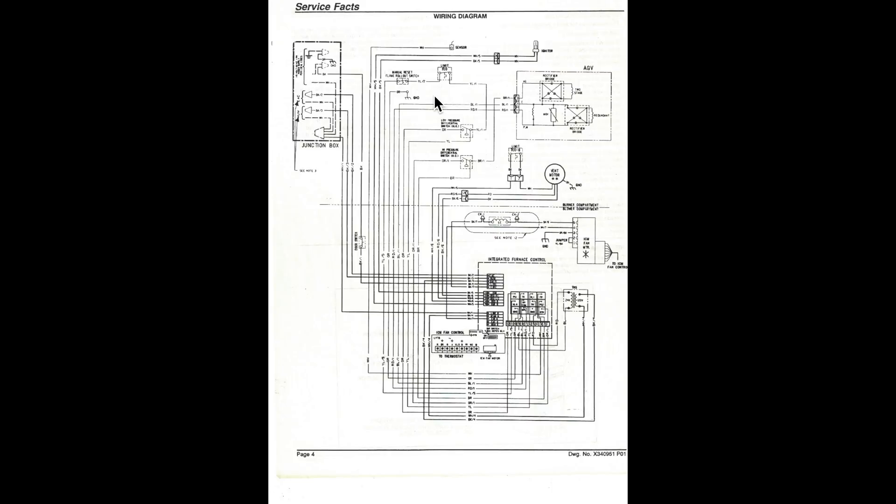Now, the limit switches here, we have three limits in this thing. One of them, that's a flame rollout switch, so it's going to be located near the firebox. Actually, on the firebox.